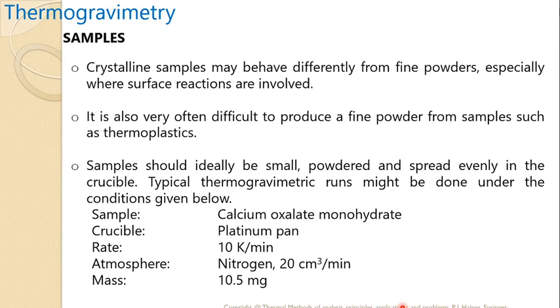Crystalline samples may behave differently from fine powders, especially where surface reactions are involved. It is also very often difficult to produce a fine powder from samples such as a thermoplastic. Samples should ideally be small, powdered and spread evenly in the crucible.